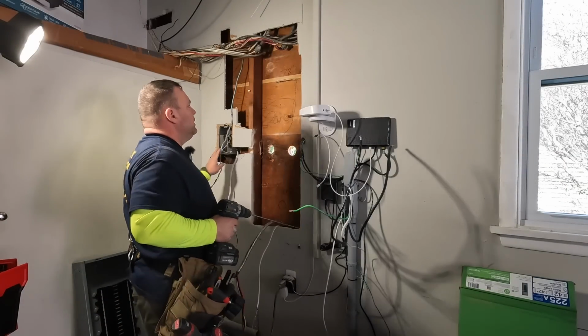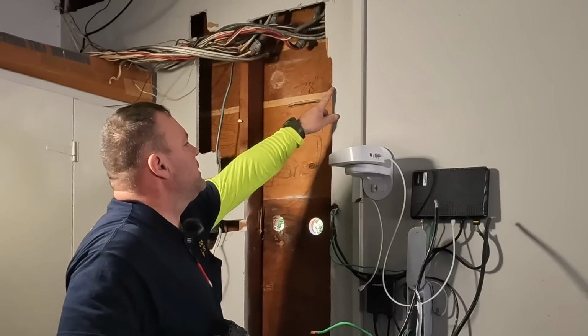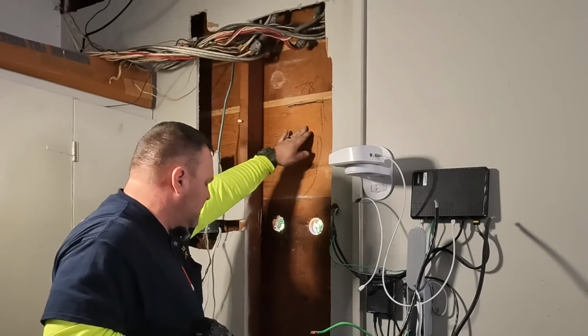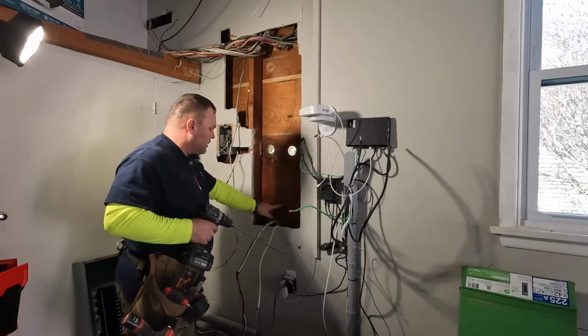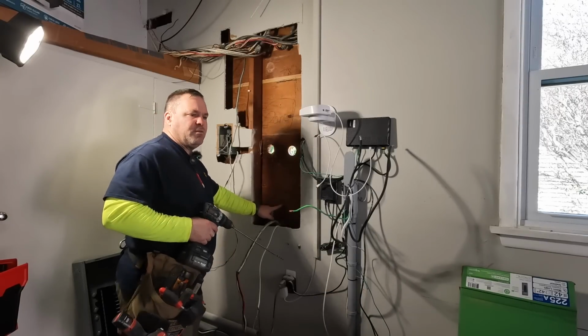I can hole saw the hole for the load side conductors going to the panel, and I can install my panel. I just put the panel cover in here and measured it to 78 inches. We're just below that, so we're good there.